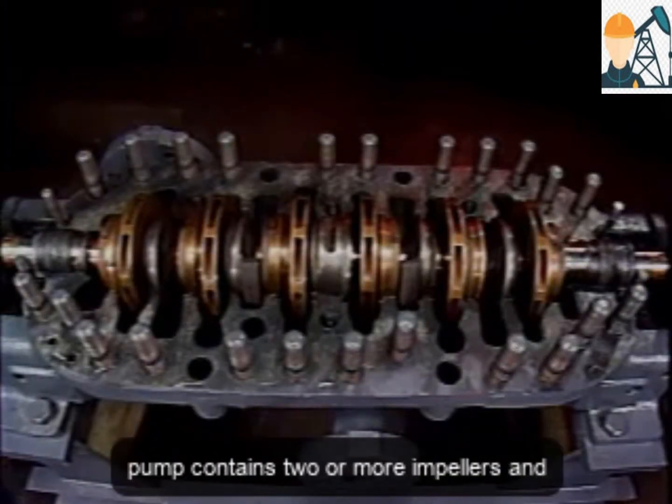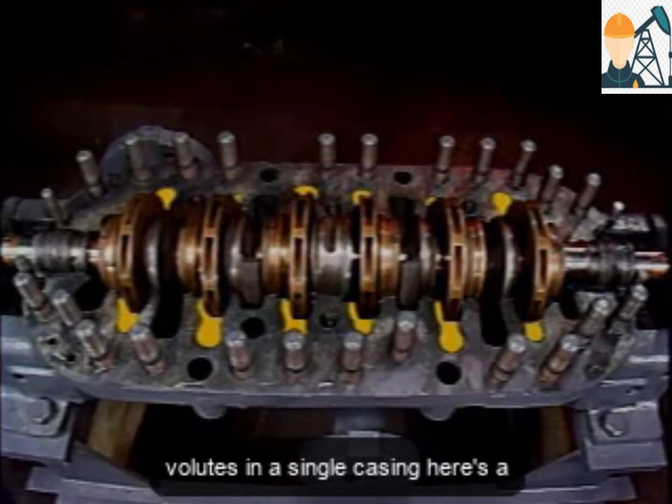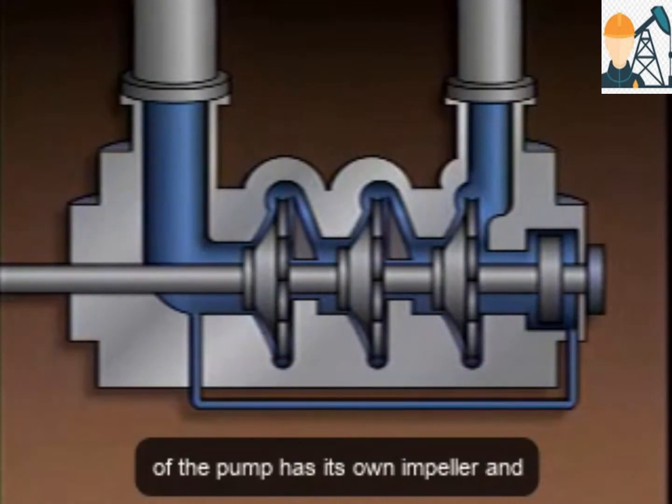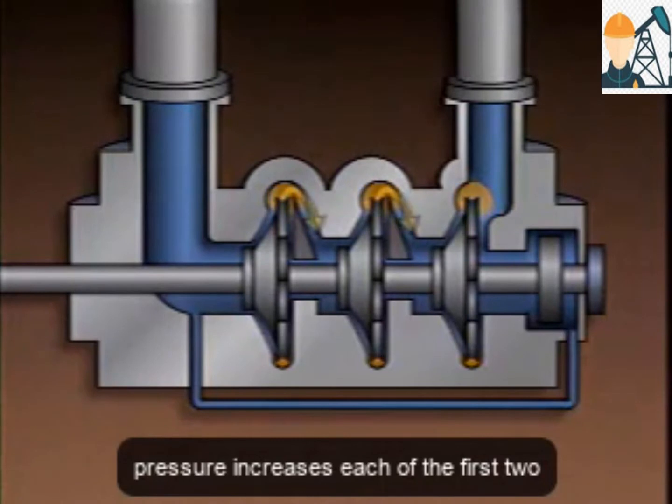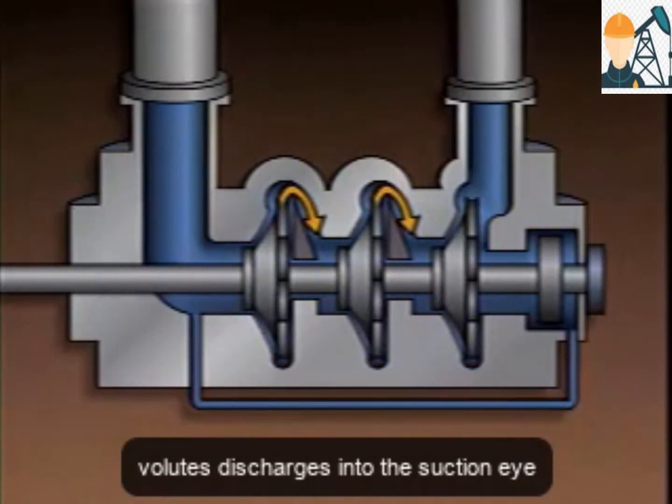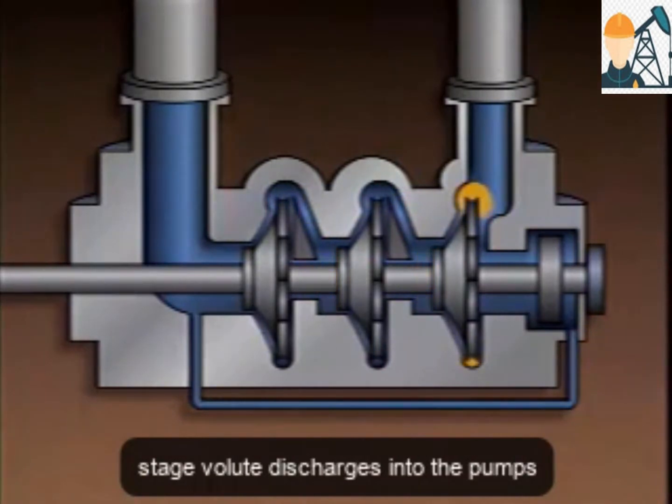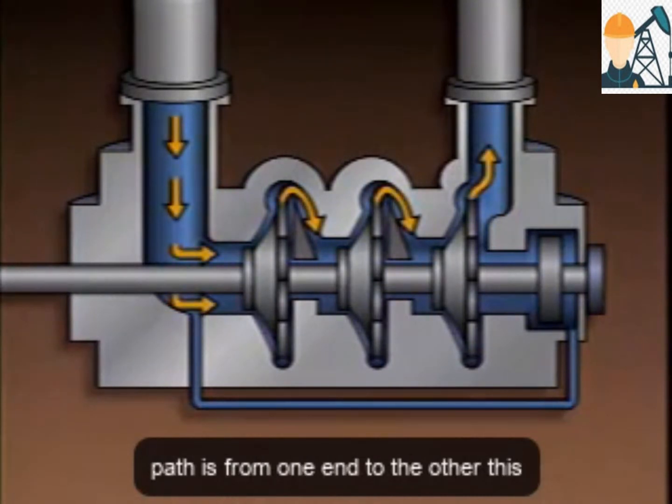A multi-stage centrifugal pump contains two or more impellers and volutes in a single casing. Here's a simplified cross-section of a three-stage centrifugal pump. Each stage of the pump has its own impeller and volute. In the volute, the liquid's pressure increases. Each of the first two volutes discharges into the suction eye of the stage that follows it. The third stage volute discharges into the pump's outlet. So, in this pump, the liquid flow path is from one end to the other.